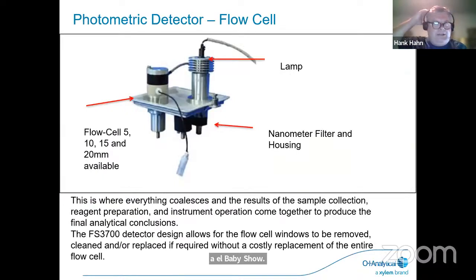So this is a breakdown of that photometric detector. Again, as I mentioned, 5, 10, 15, and 20 millimeter are available. The lamp, and then under the plate is the nanometer filter and the housing. And as I mentioned, this is where everything coalesces, and the results of the sample collection, reagent preparation, and instrument operation come together to produce the final analytical conclusion.